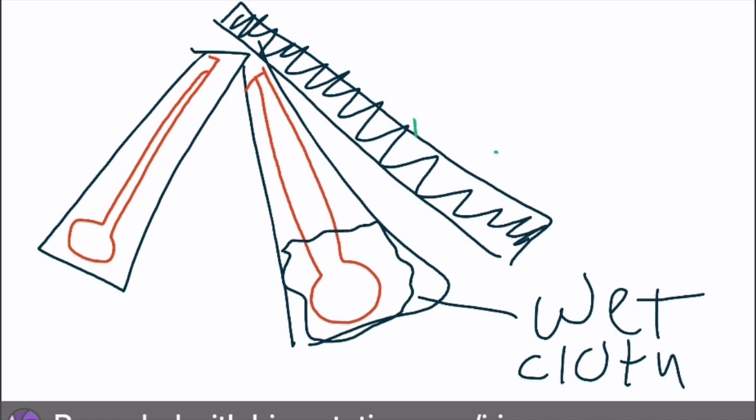The sling psychrometer has two thermometers on it that measure the outside air temperature. One of these thermometers then gets a cloth put over the bulb, and that cloth is then dipped in water. Depending on how much moisture is in the air currently, that affects directly how much of the water on that cloth can evaporate, and therefore affects how much cooling will happen on that wet thermometer. After spinning this through the air for a couple of minutes, you'll notice that the wet thermometer actually drops down the temperature that it's reading.